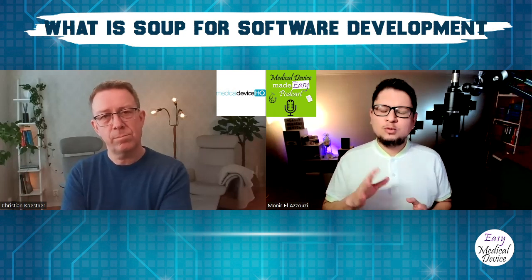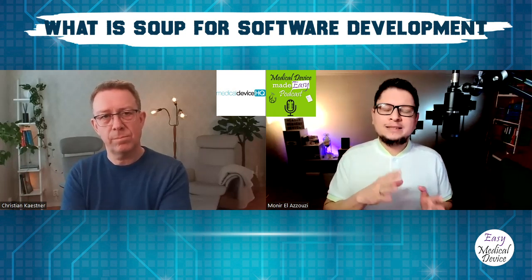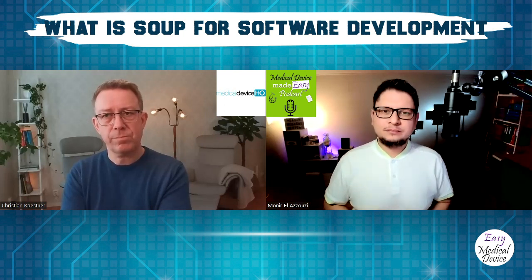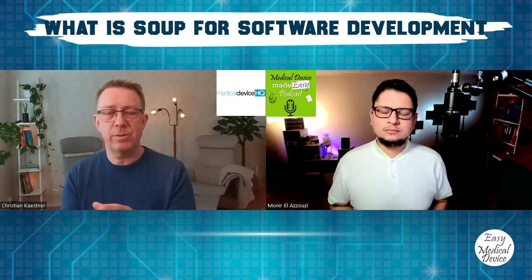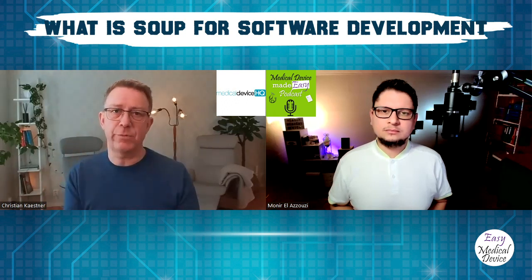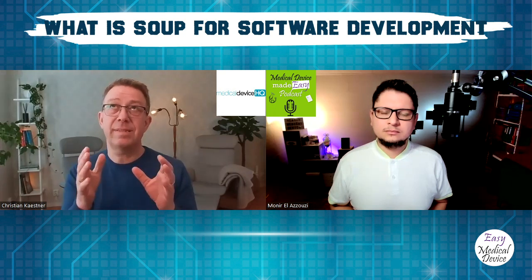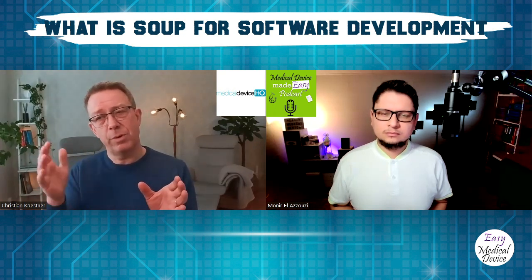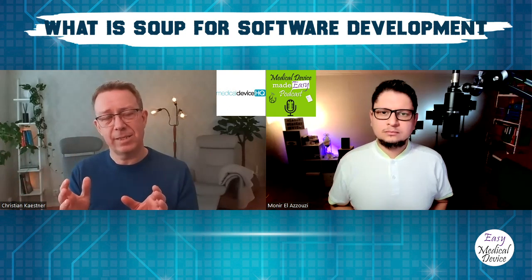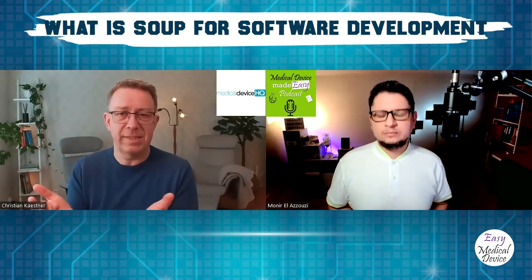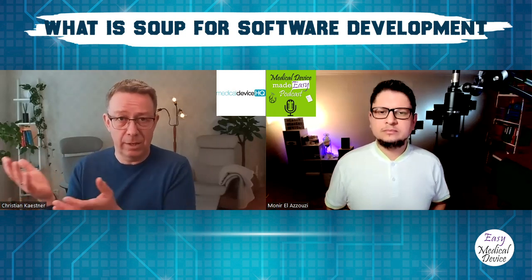We talked about 62304. You talked also about 82304-1. So what is the difference here? 82304 is intended to be a product standard for standalone software. It's intended to be the counterpart, if you're aware of IEC 60601-1, which is the product safety standard for hardware, basically including software.